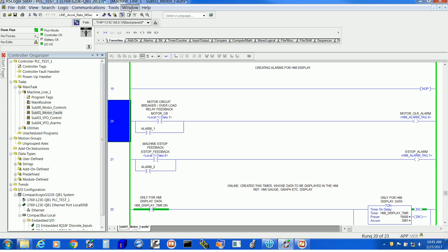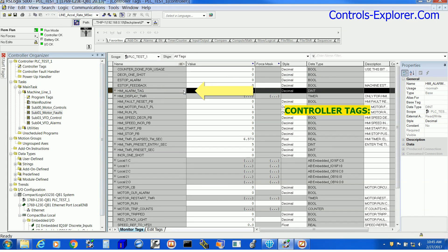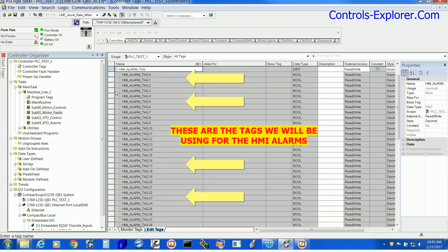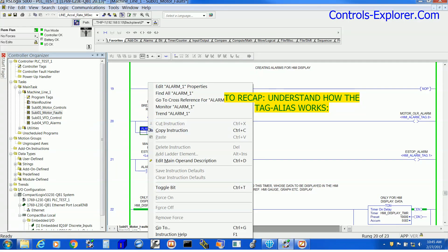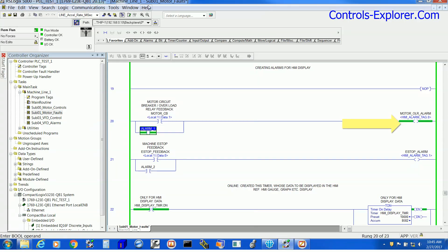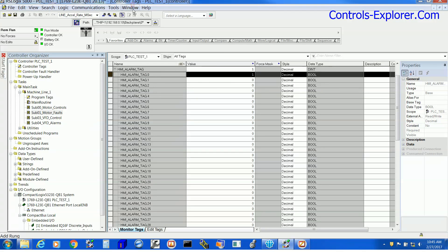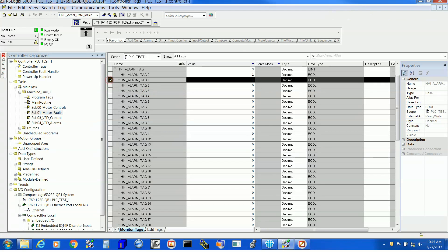Next, let us go to the controller tags and find out more. This is the controller tags, and this is our HMI Alarm Tag double integer — let's expand it. It has 32 bits, 0 to 31. Let us make Motor Overload Alarm true, which is alias to bit 0, so now bit 0 is set to 1. Same thing for the E-Stop Alarm — now bit 1 is set as true.